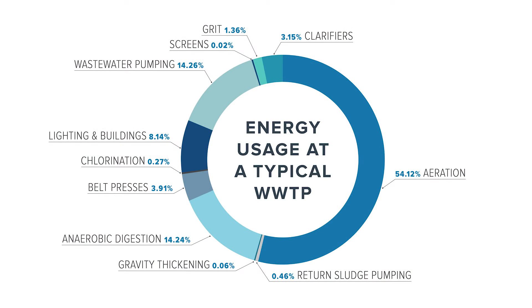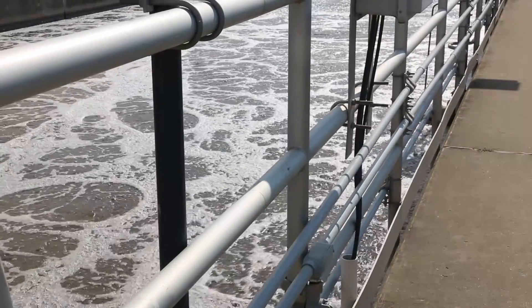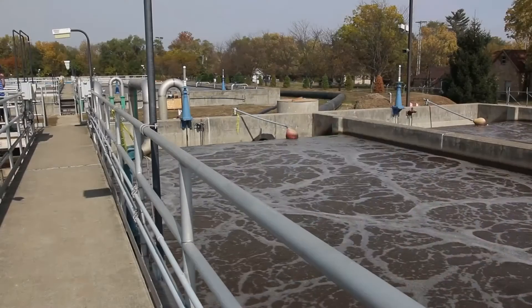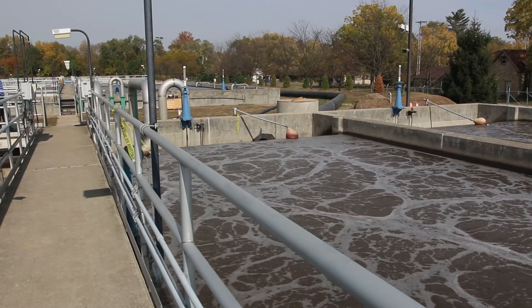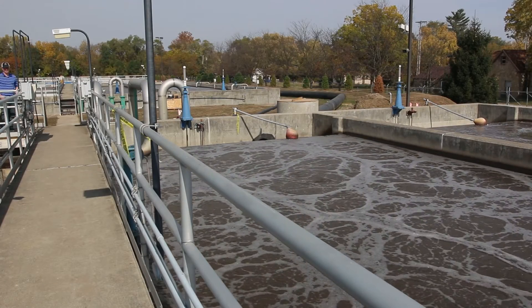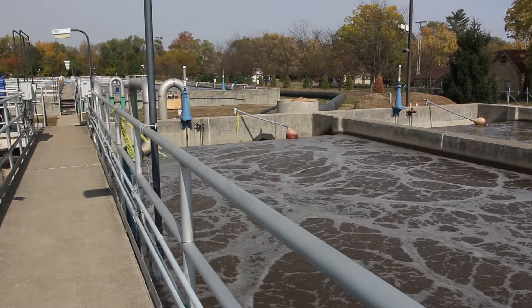At a typical wastewater treatment plant, the aeration process consumes over 50% of the energy used at the plant. This is due to the blowers being operated with a higher aeration output than necessary to achieve the permitted ammonium effluent limits. Online nutrient monitoring can help reduce the amount of wasted energy.